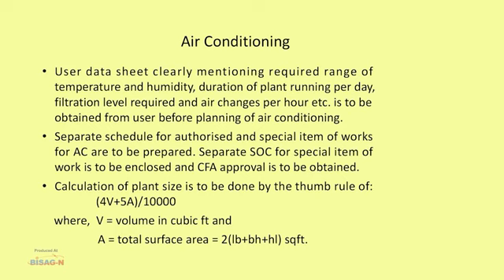A separate statement of case for special items of work is to be enclosed and CFA approval is to be obtained. Calculation of plant size is to be done by the thumb rule of (4V + 5A)/10,000, where V is volume in cubic feet and A is total surface area, that is 2 into (LB + BH + HL), where L, B and H are length, breadth and height respectively.